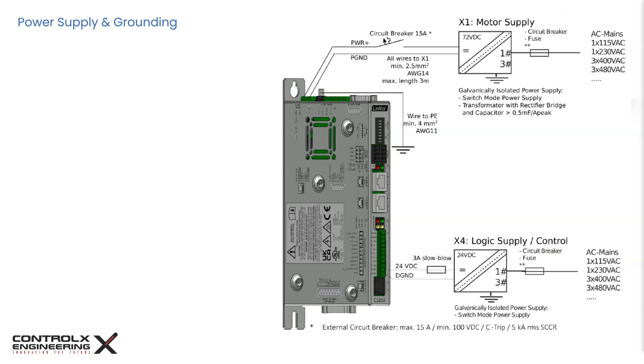Similarly, the nominal power supply for the logic supply is 24V DC, and the power source must be within the range of 22V to 26V DC. To ensure safe operation, it is a good practice to ensure all system components are well-grounded to protective earth or PE. This means that the LinMot servo and all control system components must be connected to the same ground.